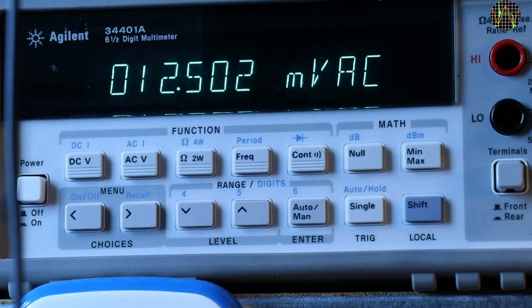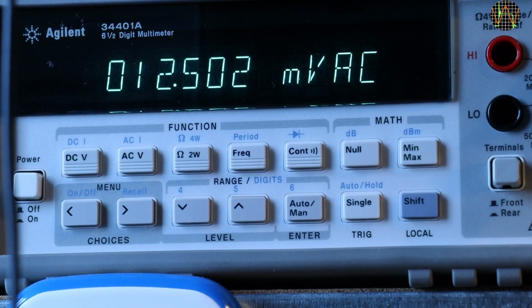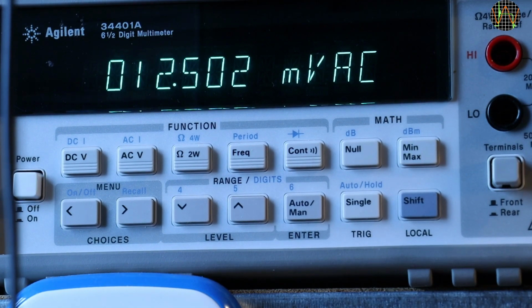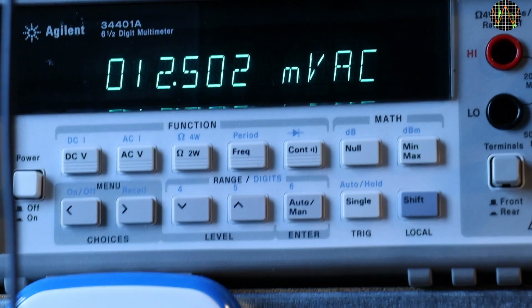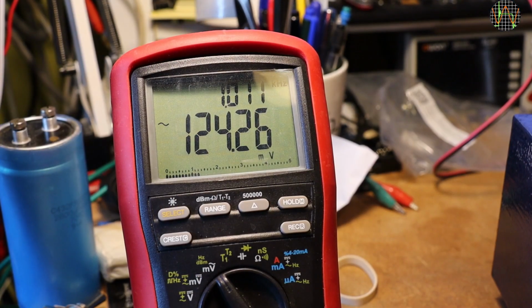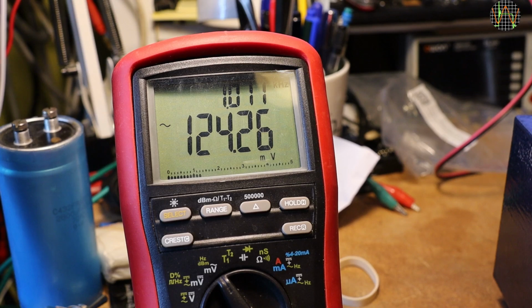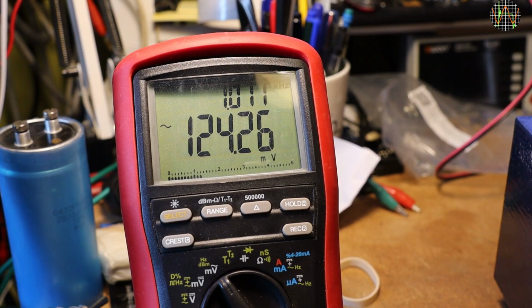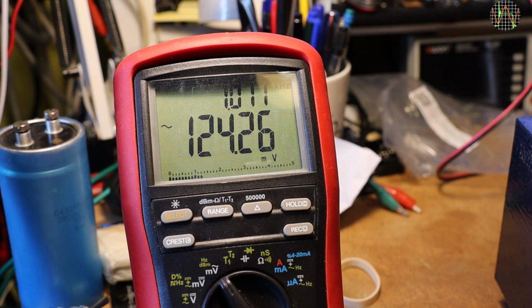The first thing the service manual wants you to do is to adjust the gain of the amplifier by applying 12.5 millivolts at 1 kHz with the range switch set to 15 millivolts. Verify that the output is 125 millivolts plus or minus 3 millivolts. Well, since it's just 0.7 millivolts off, that is still spot on, no need to mess with it.